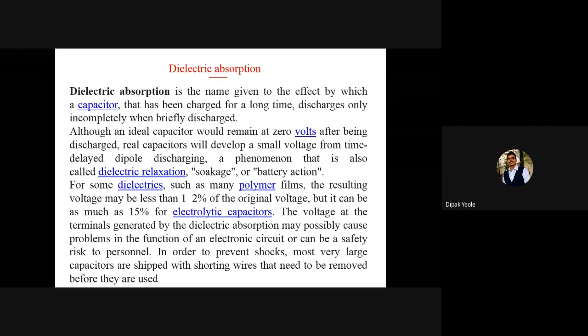The principle is the same. We have to apply the voltage first. The current is going to develop, and because of this voltage and current ratio, we will get the value of resistance. That is the principle. The dielectric absorption ratio is again the same concept, but we have to use the ratio of 30 second to 15 second, or we can use 60 second to 30 second. So this to this and this to this. Believe me, you can use the ratio as 60 second by 30 second.